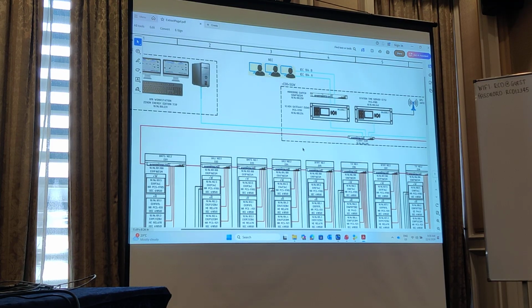So in that way, whatever is happening at the site or station, any signal being triggered, we can monitor, we can capture the time, we can capture the moment it happened, and we can read the event. But GOOSE relies not on the relay's timing, but more on the CID file's timing. They don't have a time characteristic, so they don't follow the time server's time, they follow the CID file's time.